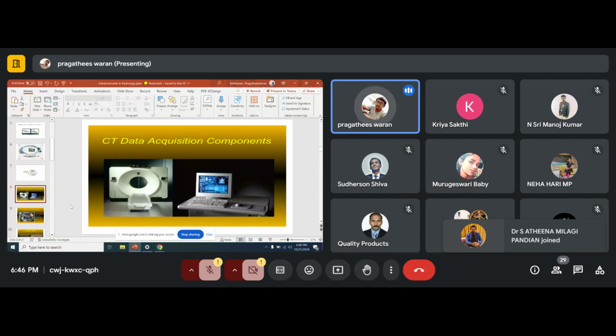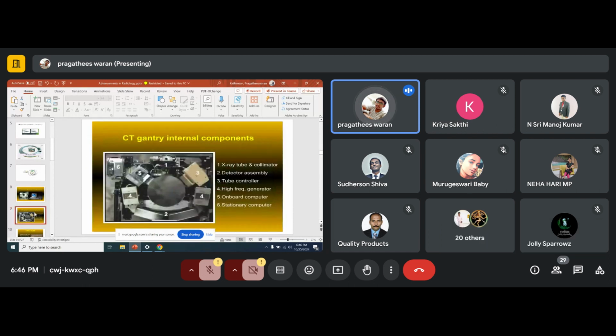Next we are going to see the detailed view of what is inside this gantry. This is how it looks. This is an X-ray tube, and below the tube the collimator is attached. Exactly opposite of this X-ray tube, the detectors will be there. The detector cooling unit and the X-ray tube cooling unit will be there. Since 1,20,000 volts is being produced, they use an oil cooling system for this X-ray tube.